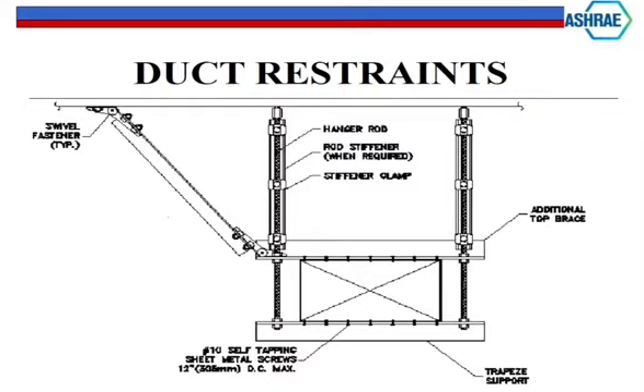Ductwork, just like piping, can be done with bracing. Here I show steel bracing - it's one-sided, whereas cable requires two cables because cables only work in tension, not compression. Steel works in both. One big problem with ductwork is it's such light gauge - you cannot just bolt onto a piece of ductwork, it'll just rip the steel out. So you end up having to put steel on top and bottom to keep the rectangle shape, with sheet metal screws holding it. This keeps it as one rigid rectangle, then you have your braces off the steel work transferring forces.